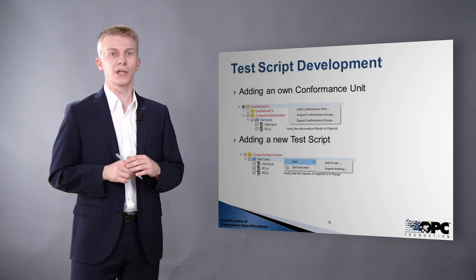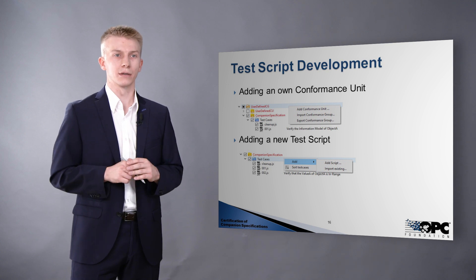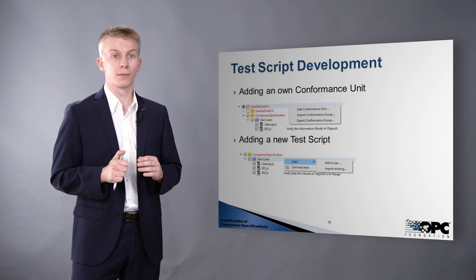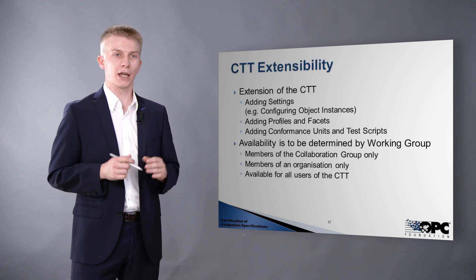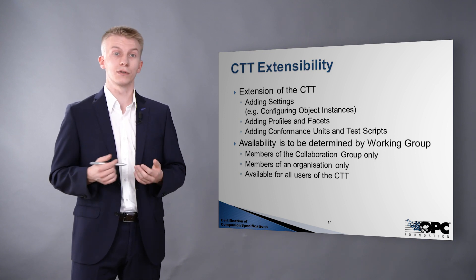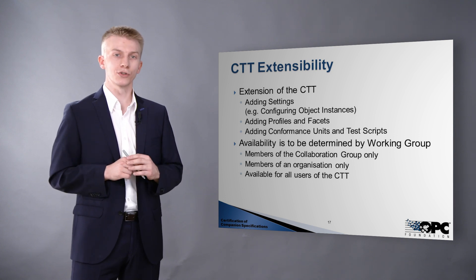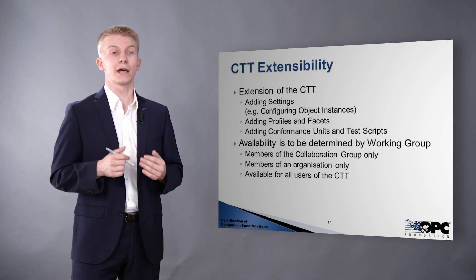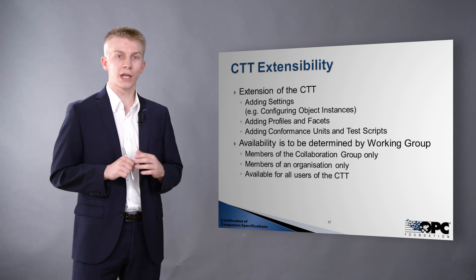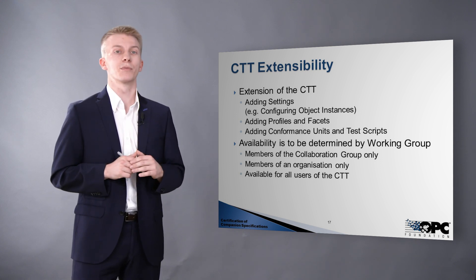Test scripts can easily be integrated into the compliance test tool. For a conformance group you can add your own conformance unit, export existing ones, and import new conformance units. The same way you can add new scripts to it. The CTT can be extended with additional settings like configuring object instances, or configuring minimum and maximum values that might be more restrictive than the companion specification itself. You can also add profiles, facets, conformance units, and test scripts. These extensions are the responsibility of the collaboration group, and we understand they need to be able to define whether developed extensions are accessible to everybody, just members of an organization, or only members of a collaboration group.